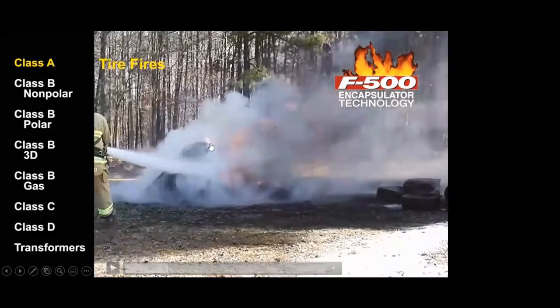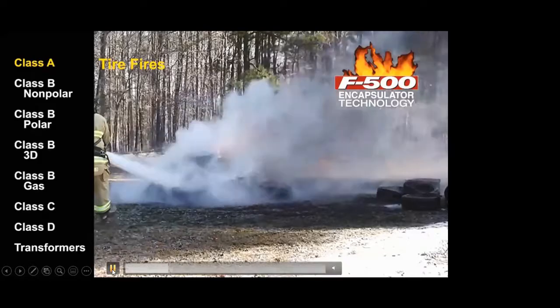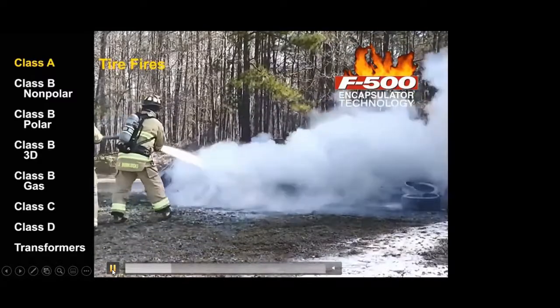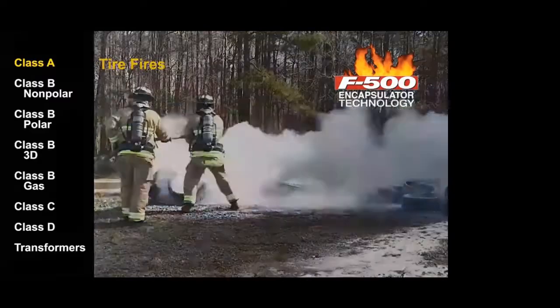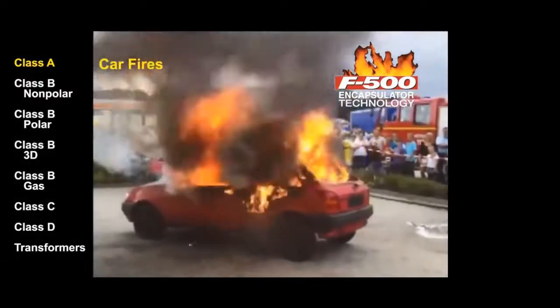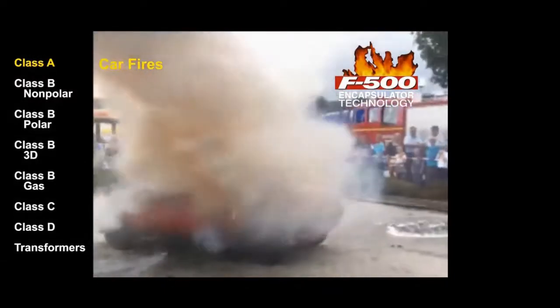Again, I want you to see the tires are still on fire, but all the black smoke is dissipated. That's because the agent is interrupting the free radicals, preventing them from coming together to form more soot and smoke. So in addition to the fast knockdown, I stopped it a little too late. You can still see the fire, but no smoke. This again is a 20-gallon-per-minute nozzle.